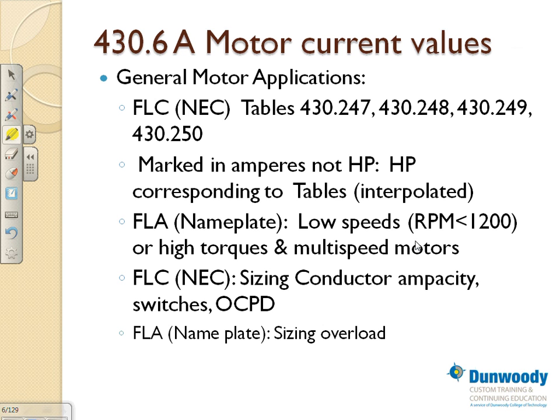But the challenge is the amps. The problem with motors, they don't come with amp rating. Most motors come with horsepower rating. And there are so many manufacturers of motors, guys. So the ones smarter than me decided a long time ago to group all these motors based on voltage and horsepower and assign to them a code full load current value that will be typical for almost all the manufacturers. And that's where they came up with these tables.